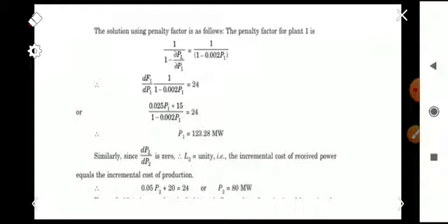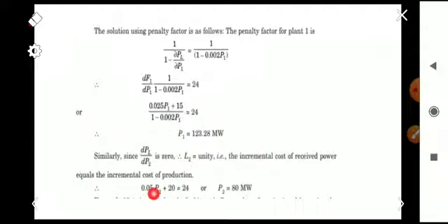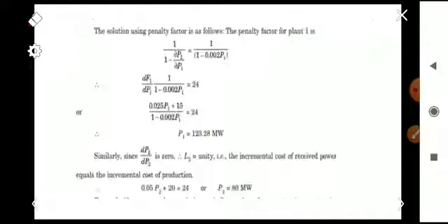For plant 2, ∂PL/∂P2 = 0, so the penalty factor becomes 1/(1−0) = 1, which is unity. The incremental cost of received power equals the incremental cost of production, giving 0.05P2 + 20 = 24, so P2 = 80 MW. Both methods — coordination equations and penalty factor — yield the same results.